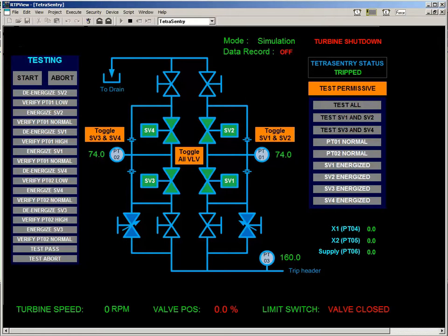So you wouldn't know if SV2 can hold the pressure if SV1 is fully sealed until SV1 opens. So let's look at what that does to these pressure gauges.